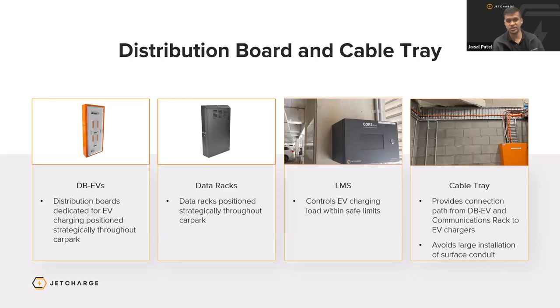The data racks are also positioned strategically throughout the car park to ensure that we do not exceed the 90 meter limit for category 6 cabling, as running more than 90 meters would probably require additional data racks or fiber connections between the data racks. We have obviously the load management system that controls the EV charging loads within the safe limits of the building. And cable trays are especially important because they provide a connection pathway from the DBEV to the chargers and from the communications rack to the chargers. So they will require their own dedicated communications and power cable trays. And the other point is that they avoid large installations of surface conduits, which can not only be unfeasible for larger installations, but can also be aesthetically not very pleasing. Next slide.